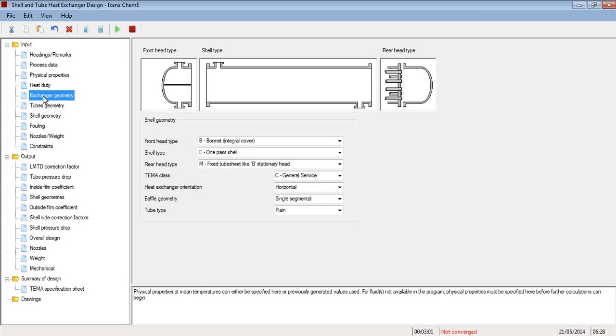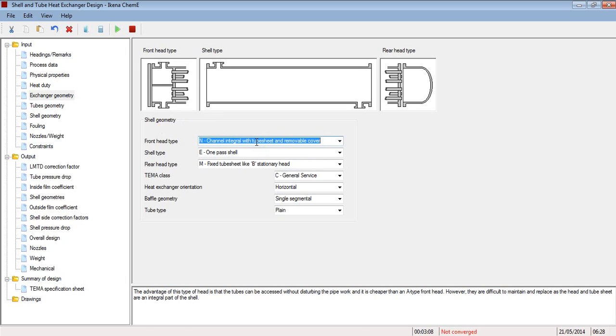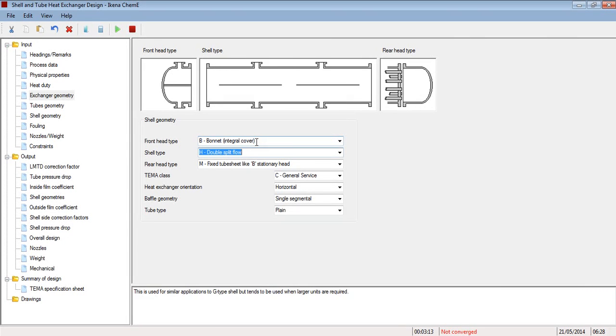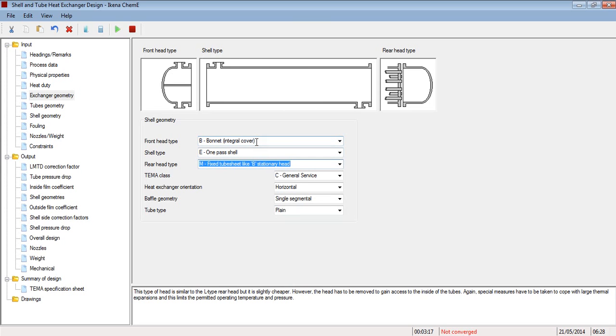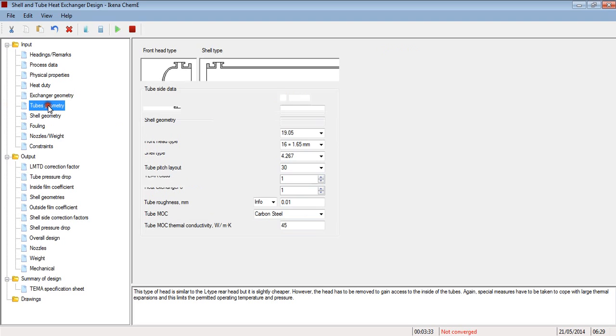Okay, now on this screen you can define the geometry of the heat exchanger: the head types A, B, C, D, N, the shell types, all of these are available within the program, and the rear head type. Okay, all of these are available, but we will use the BEM type, the most common one. This is the TEMA class here, the heat exchanger orientation, baffle geometry, tube type. Since we are working with liquids, we will use plain tubes.